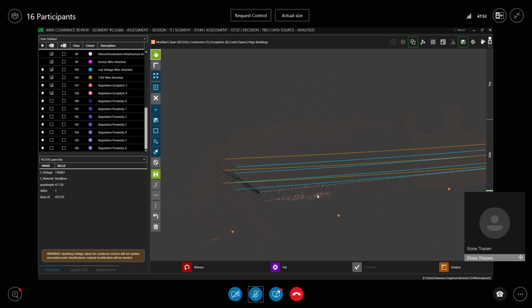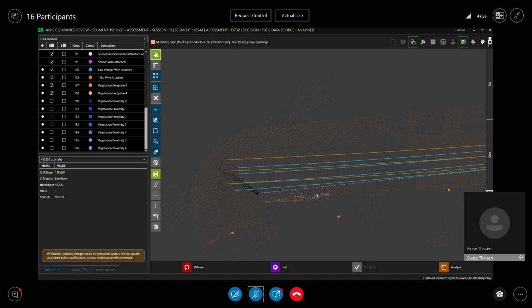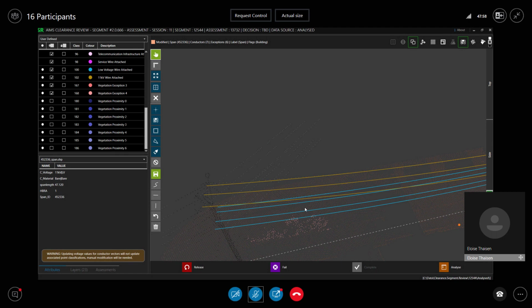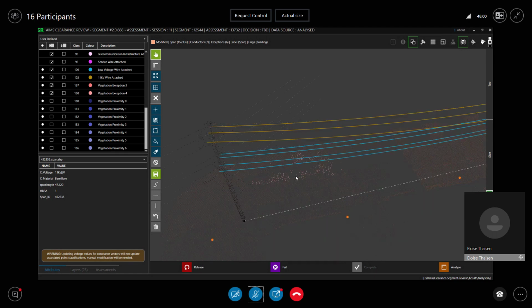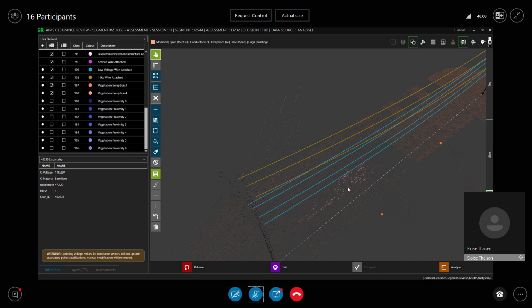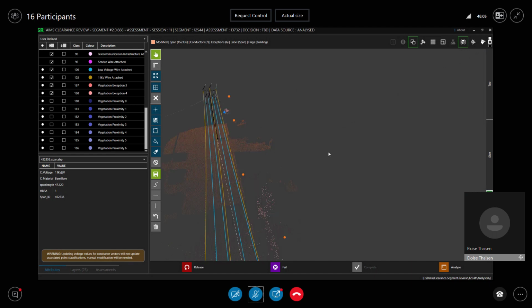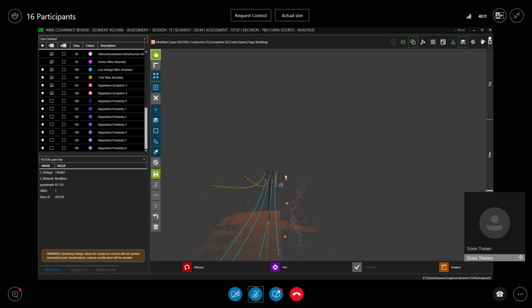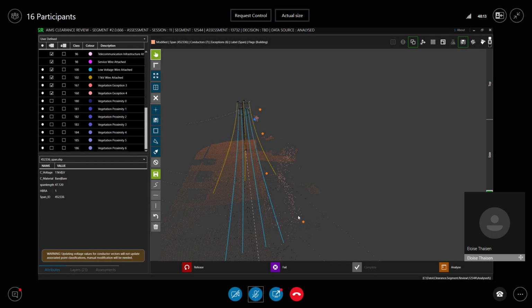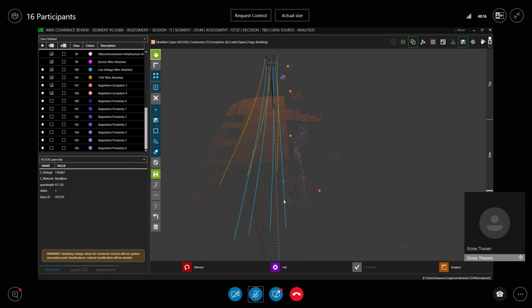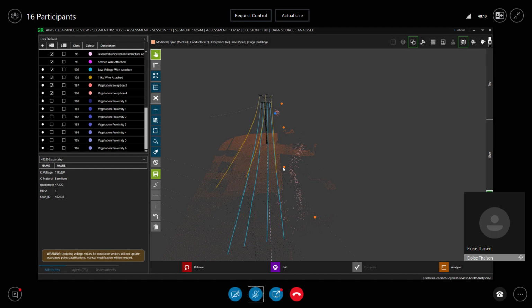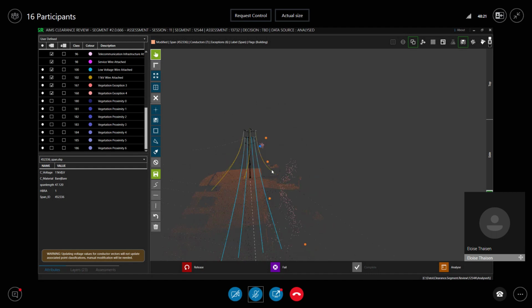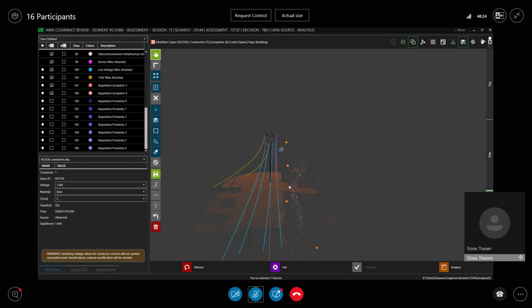It's all based on vegetation distance to conductor, and on vegetation encroachments set by regulatory bodies in Australia, because Australia has very strict bushfire regulation and control. There are distances required to be assessed from the conductor, so the distance from here to here is how this vegetation gets categorized into vegetation exception 3 and so on.